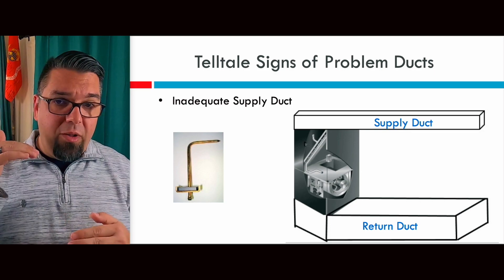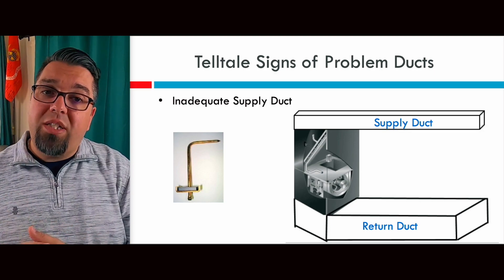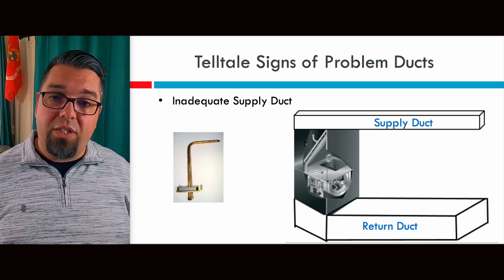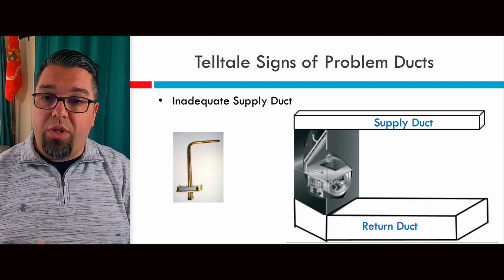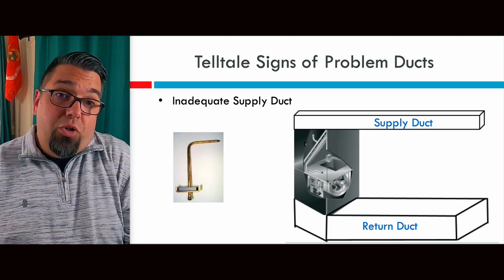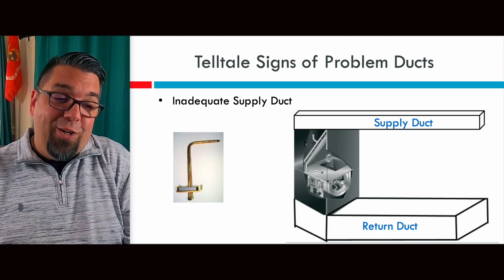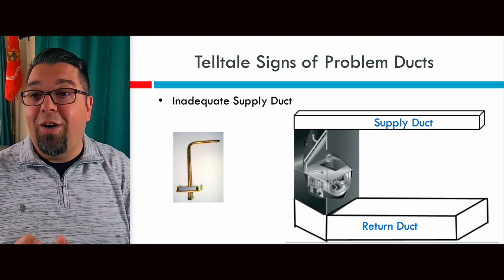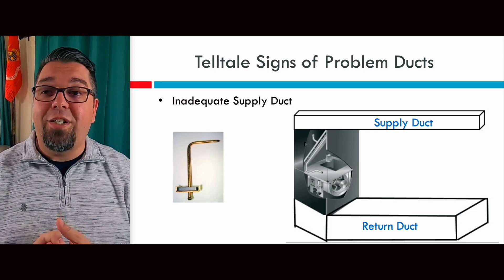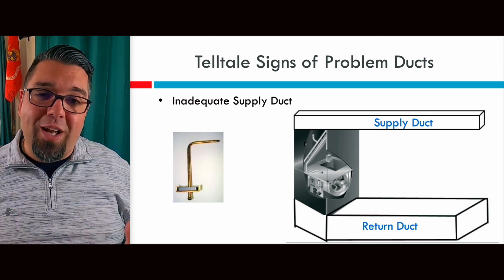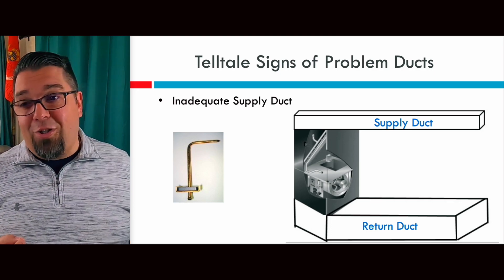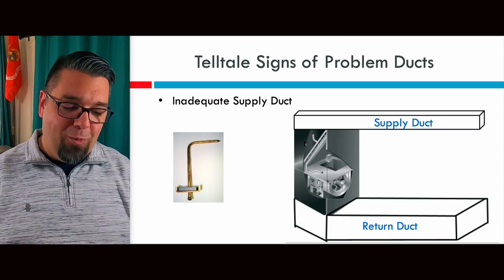Supply and return should be fairly balanced. If you have inadequate supply ducts, you're going to see much higher static pressure in the supply when measuring with a static pressure probe and a simple dual-input manometer. You could use an incline manometer or something that uses water like the old Dwyer gauges — most people don't use that anymore, particularly because if you have really high static pressure, it could suck that fluid right into the return. I've done that more than once.